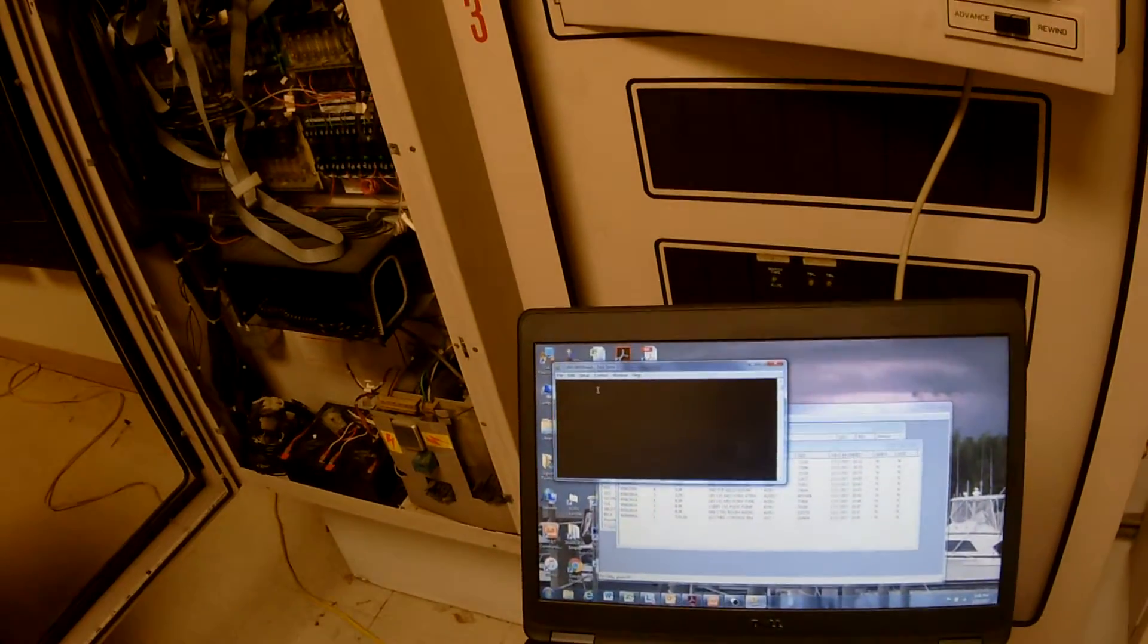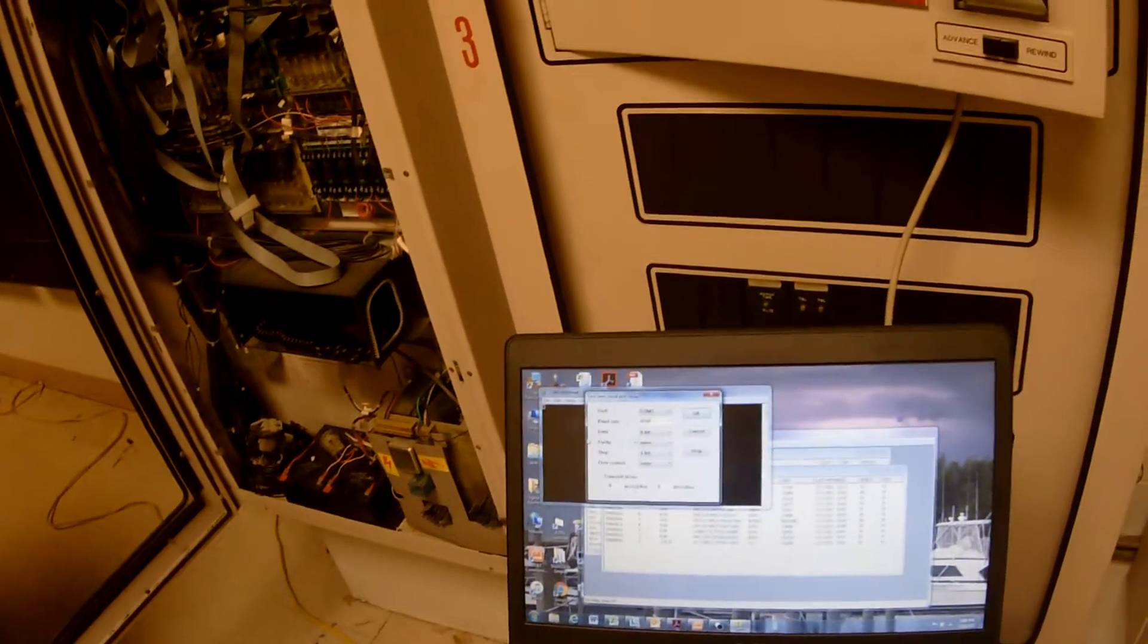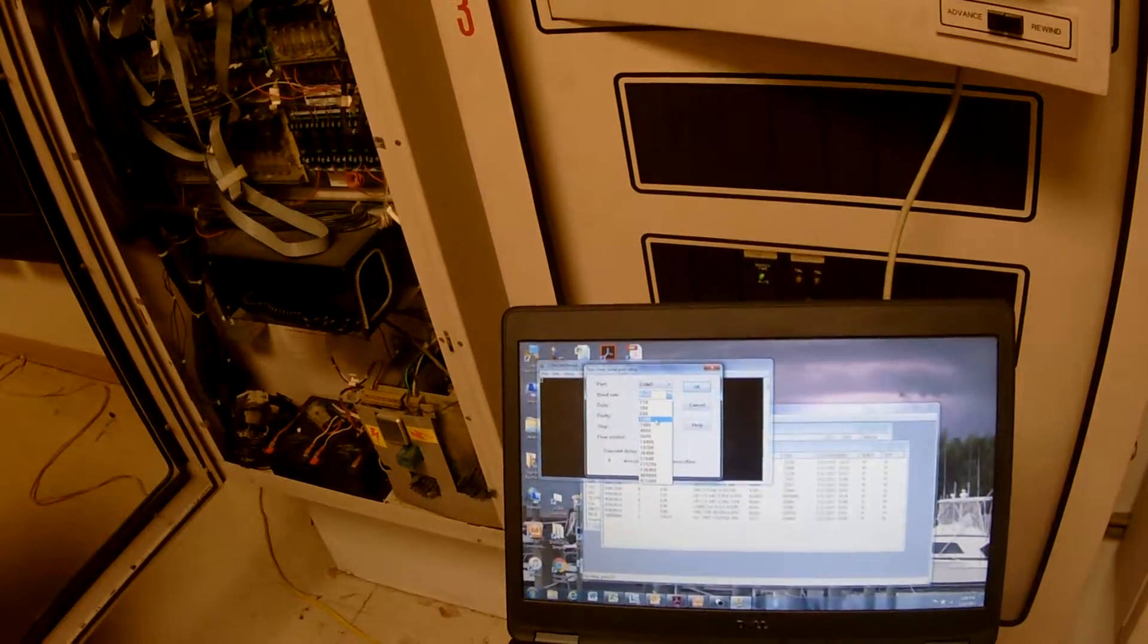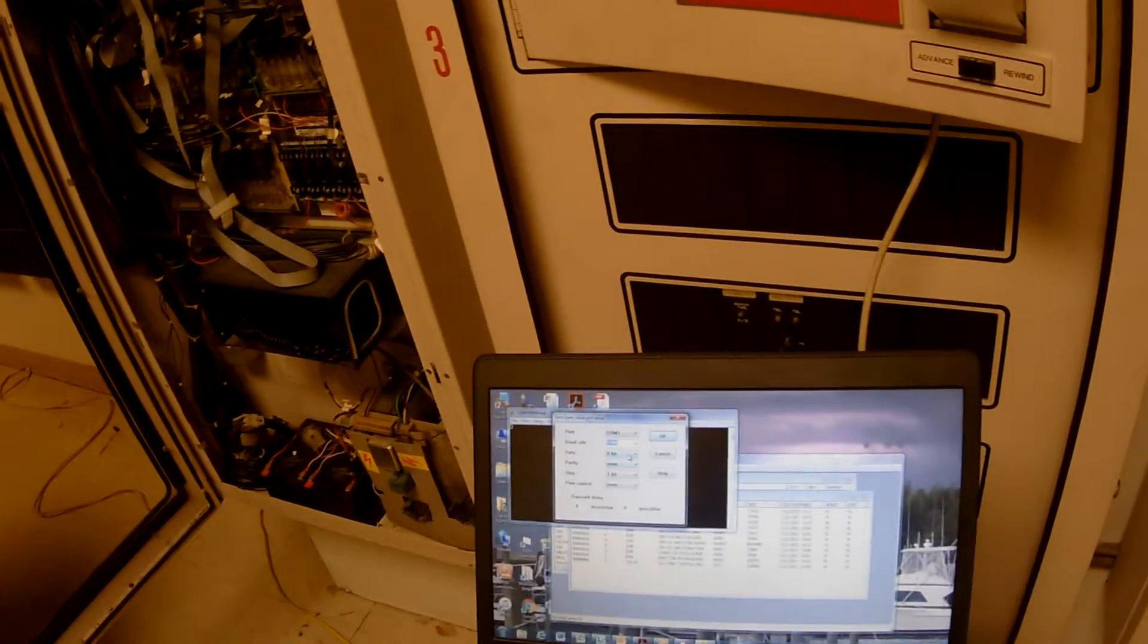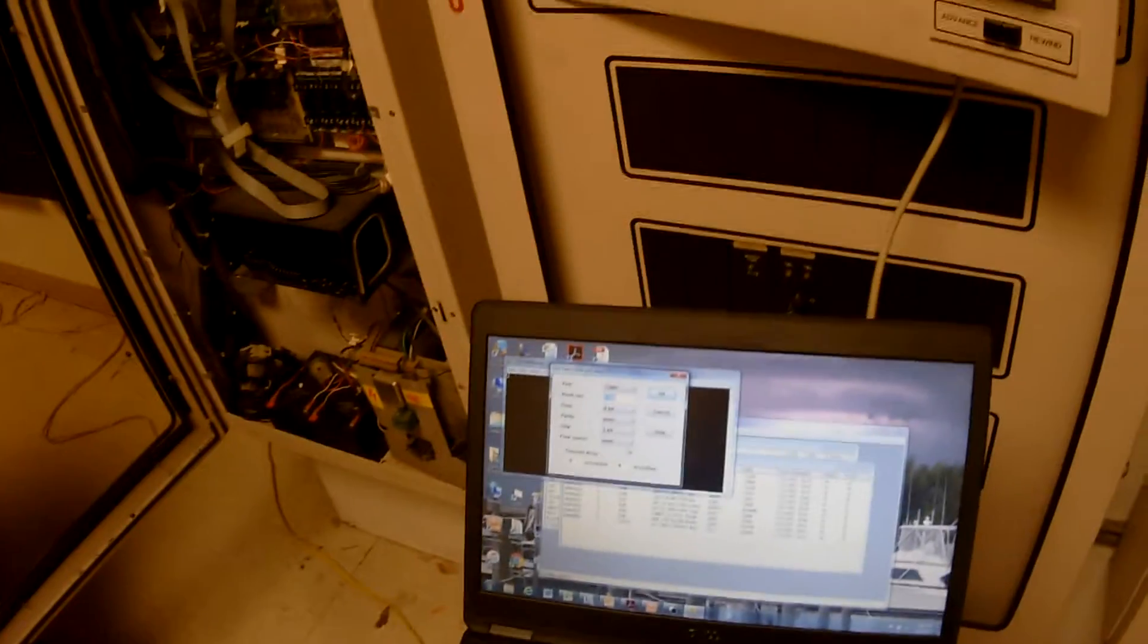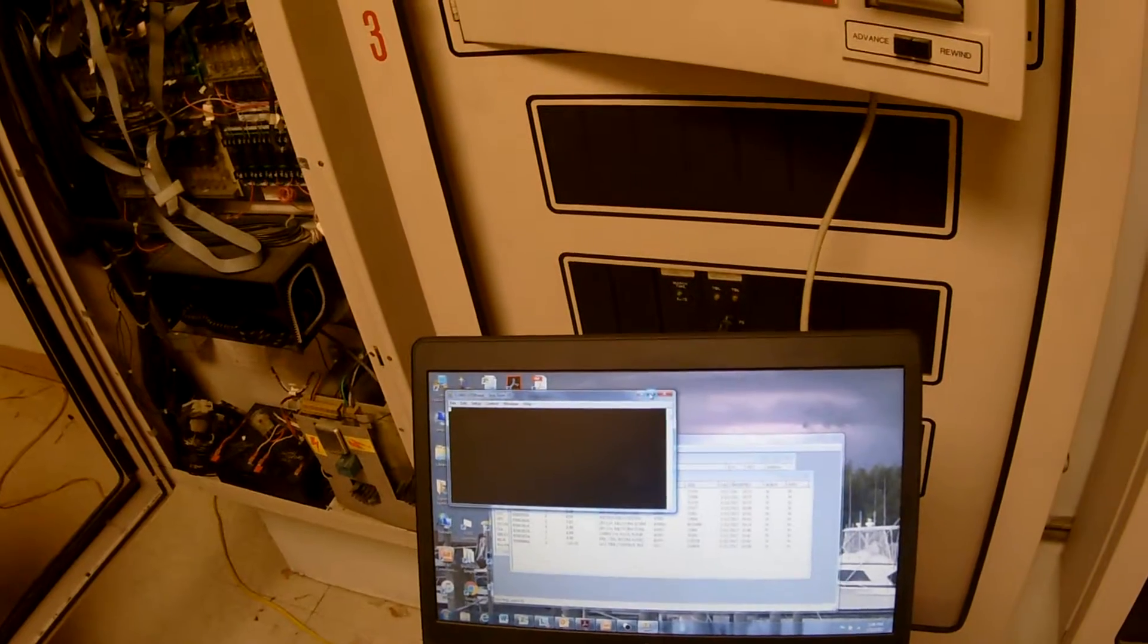Now we go to Setup, and we go to the serial port. Now this panel here communicates on 1200 baud rate, so it comes default 9600. We're going to switch it to 1200. The default data bits, and the parity, and the one bit - that's all default, that's all good. So we'll hit OK. Let me go ahead and expand this window, make it nice and big for us, and I'll go ahead and plug my port in here.